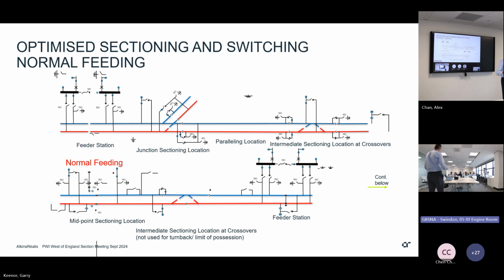There are all sorts of other issues that will need to evolve, particularly your emergency isolations - how do you actually go about isolating? But in effect, you can use your circuit breaker on your incoming feed, which can wipe everything out to clear any fault. You then use all your isolators around where your fault is, and you can reclose the circuit breaker. That can all happen in very few seconds, 2 seconds or less, so physically that can be done with very little disruption.